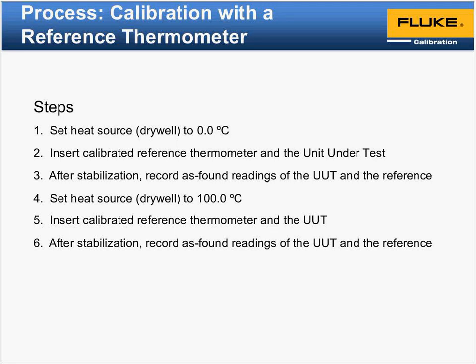Okay, next question is, is a simulator a standard, with acceptable specifications? That's kind of a loaded question. So with a simulator, it's like with anything else. There's usually several levels of accuracy that you can get, depending upon range and accuracy requirements, and that determines what grade you're going to purchase. It may not be as good as a multi-function calibrator, which is definitely not going to be up in these processes. We're used to the bigger box calibrators. Certainly as far as PPM goes, maybe from 100 parts to 20 to 5. Again, it just depends on the actual simulator you offer them, and what they're capable of as far as the range.